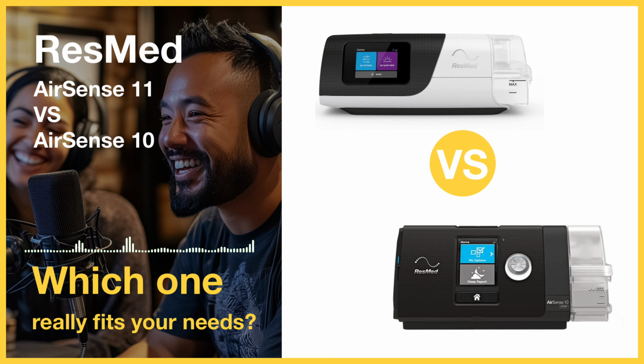Correct. You can either set the humidity level manually, level 1 through 8, or use the automatic climate control setting. Auto is usually easier, right? Generally, yes. Climate Control Auto aims to maintain an optimal humidity level, typically around 85% relative humidity, and temperature, automatically adjusting to prevent dryness but also avoid condensation or rainout in the tube and mask.